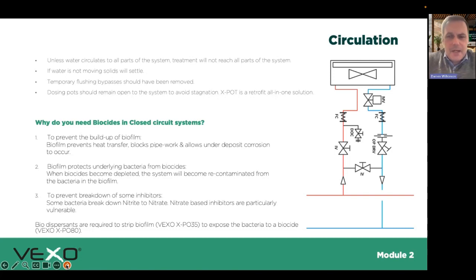On biocides, going back to bacteria, we want to add a biocide to a system typically to deal with the build-up of biofilm in the first place, so we don't want bacteria to flourish, and we don't want to lose any of our inhibitor either. So if your contractor is adding a biocide, it's very important that it gets added with a biodispersant. A biocide will kill the bacteria, but it's got to get to it. If it's protected beneath this biofilm, nothing will happen, because the chemical can't reach the bacteria. Adding it with a biodispersant breaks up that jelly-like substance and allows it to then kill the bacteria.